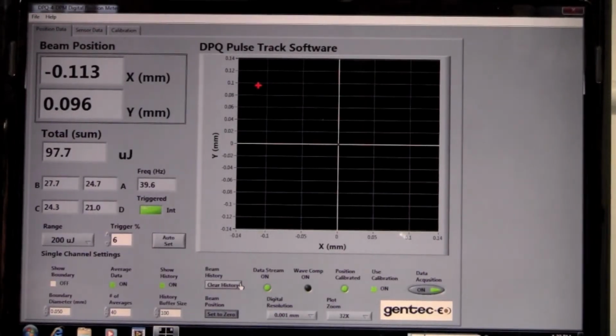Now we'll take a closer look at 4-track operation and software. On the main software screen, you see a large XY graph to the right that displays and tracks the centroid of the laser beam. You can see the red plus that represents the center. We're operating in the calibrated mode, and the laser beam is currently at about minus 0.37 in the x-axis and plus 0.96 in the y-axis.